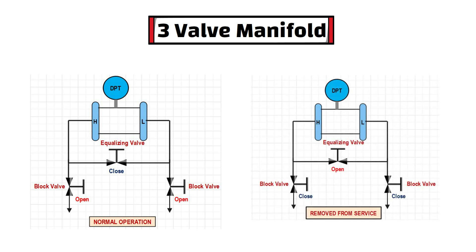On the flip side, when DPT is removed from process for service purpose, both block valve is in closed position and equalizing valve is in open position.